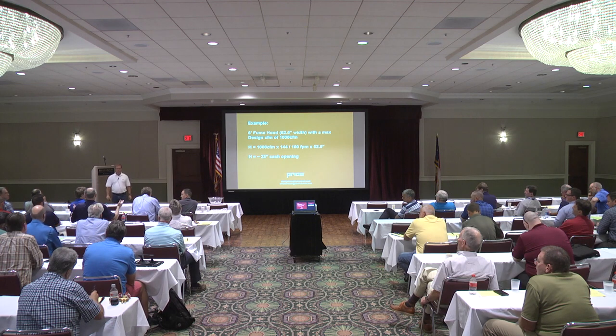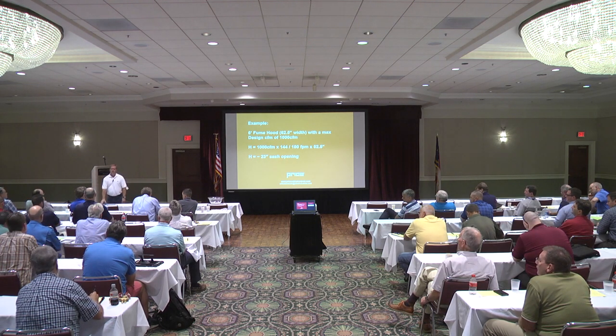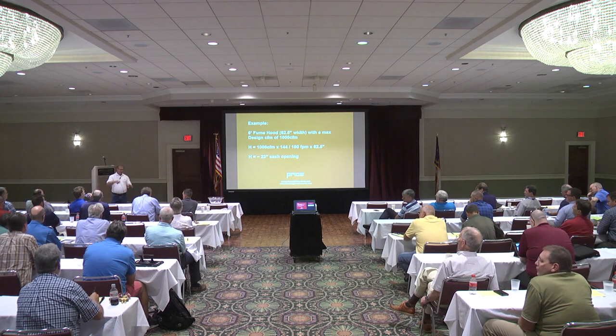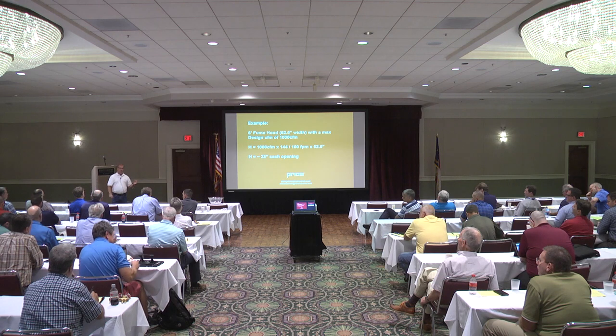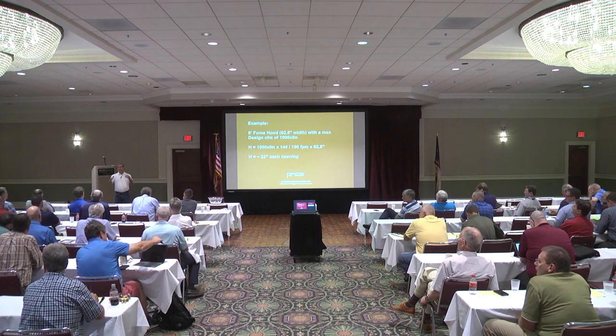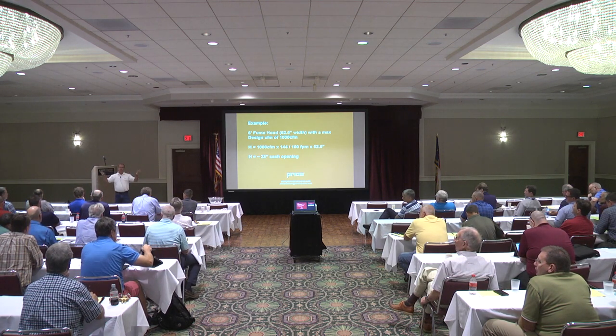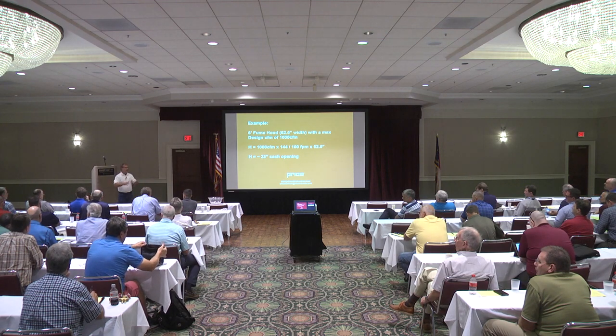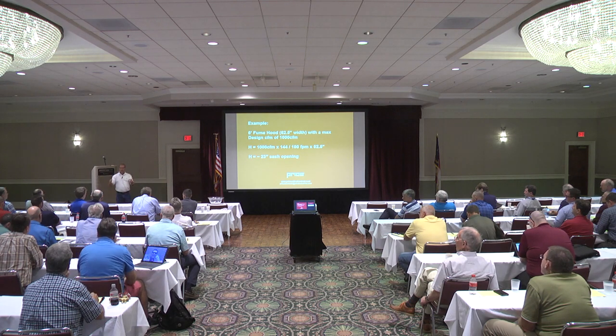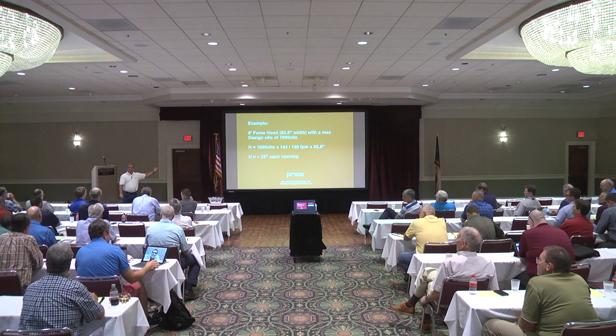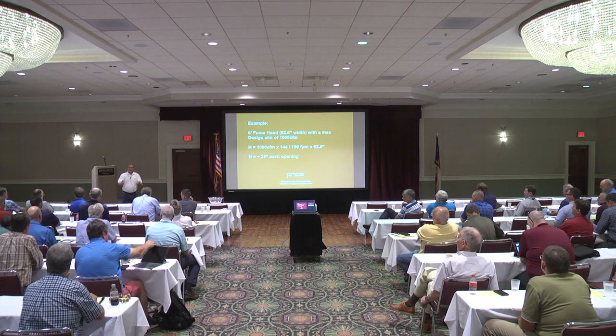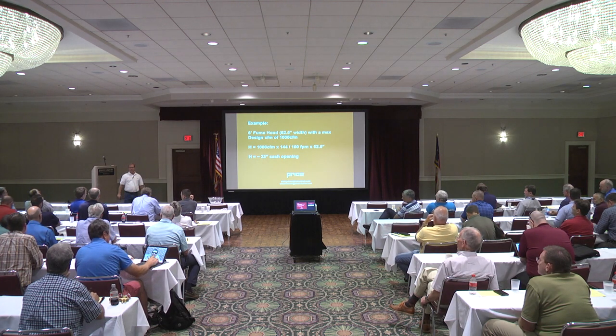A university has a standard, schools have standards, they tell you to test them at 18 inches. So that's another entity, the university, the pharmaceutical company, whatever. But you're taking that as information outside of the design document. The design document told me 100 feet per minute, 1,000 CFM. Until I deliver that to the project, I can't deliver it to the owner. The owner may want something different, but we haven't given him the project yet. I've got to deliver this thing per the contract documents before we get to that point.